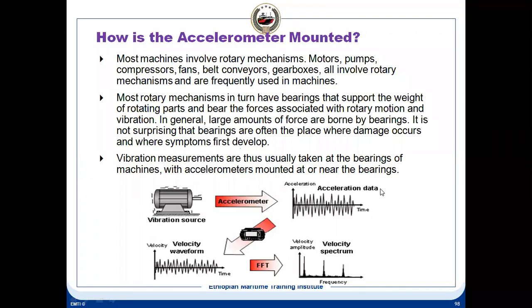It is basically used on compressors, fans, gearboxes, even on the generators, on the main engine, everywhere you'll find these pickup sensors. The pickup sensors are the accelerometers. The reading from the sensors comes to a PLC unit, which will convert this into 4 to 20 milliamps and give it to the PLC input-output sections. And whenever the vibration exceeds the limits, it will activate an alarm or it can trip the machinery.